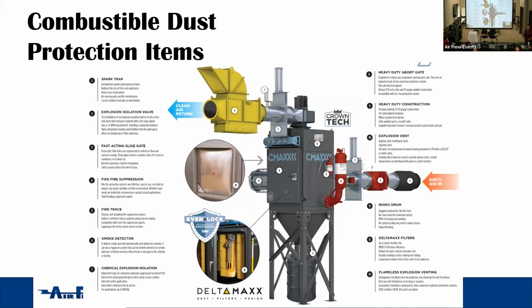If your dust comes back with a KST of anything above 0, you need inlet protection. On your inlet protection, you can have multiple devices depending on the KST you have, and we'll also lay it on the chart that you have in front of you. You can have an EIV, which is an explosion isolation valve. You could have a fast acting slide gate, or you could have a chemical boom of some type that actually will put a pressure back in and stop the explosion from going back in.